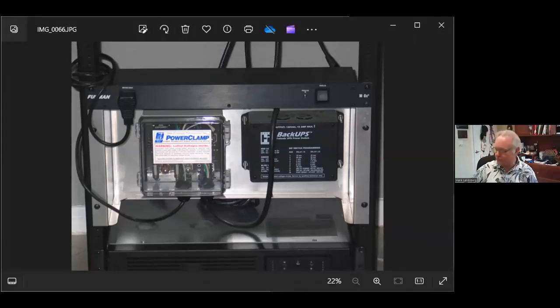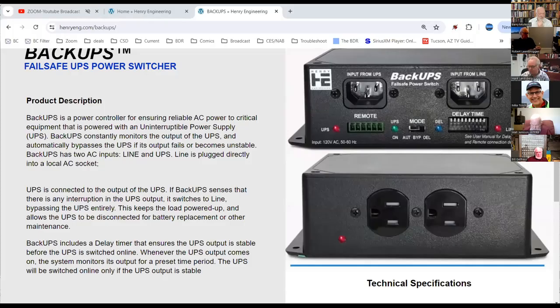So that's what the backups does. It backs up your UPS power supply. So if you have any problems with it, or if it senses problems with it, it'll bypass it. And of course, once it's bypassed, then you can unplug it. Your rack stays live, everything stays on the air. Then you can replace the batteries in it and fix it or do whatever you got to do.